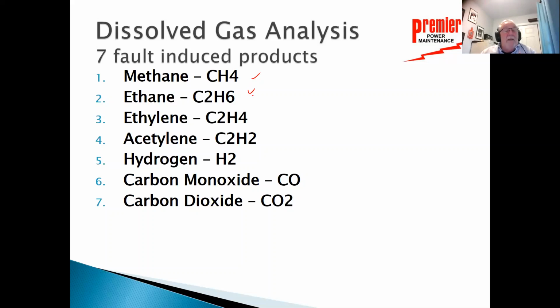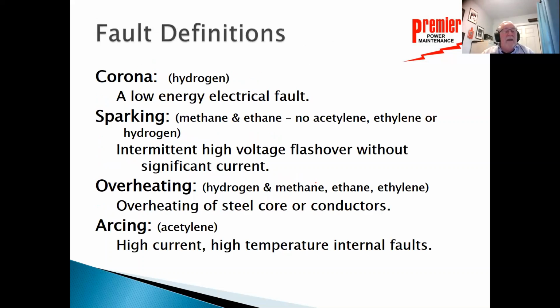Methane, ethane, ethylene, acetylene, hydrogen, carbon monoxide, carbon dioxide. I can look at those gases and the arrangement of those gases and get an idea of what may be happening inside that transformer. For instance, corona. If I see a lot of hydrogen in there, that would be an indication of possible corona, a low energy fault inside that. Sparking and arcing, methane and ethane without any acetylene.